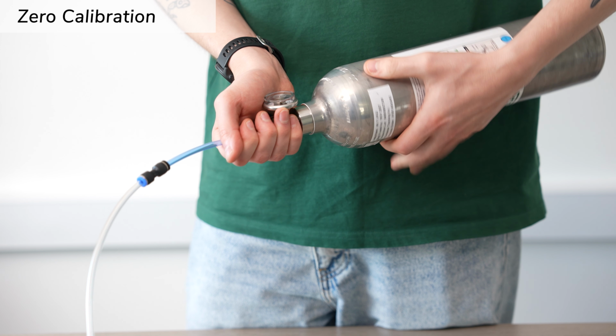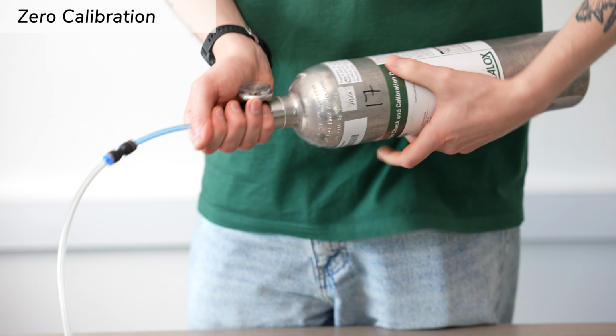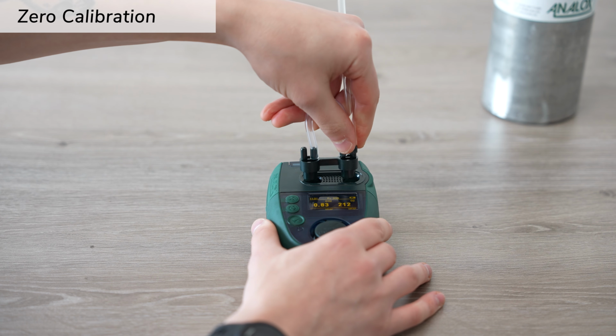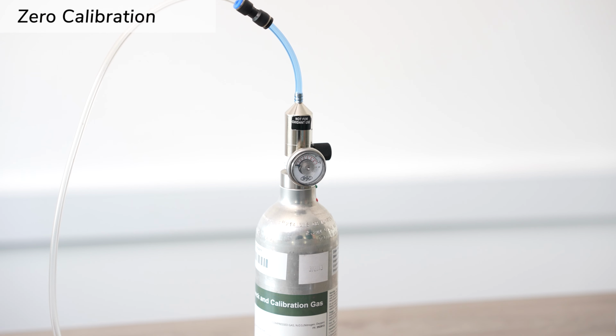If you do not have these exact calibration gases, you can adjust the calibration value, but we will show you how to do this later. Let's start with the CO₂. When you perform a zero and a span calibration, the zero calibration should always be completed first. Connect your regulators to the 100% N2 calibration gas bottle. Using the adapters provided with the Aspida, connect the tubing to the sensors.